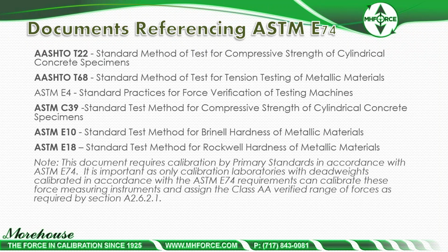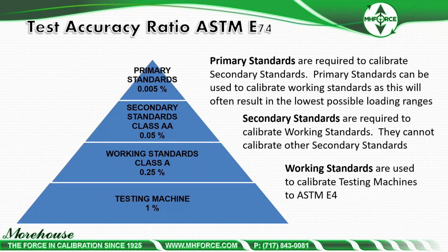Documents, jumped ahead of myself. The documents referencing E74, the standard. We're going to talk about E74 first, but here are some documents, a list of them. There's AASHTO T22, AASHTO T68, ASTM E4, ASTM C39, E10, and E18. If somebody is doing verifications to E10 and E18, their specific needs call out to have the force measuring device calibrated in accordance with ASTM E74 using deadweight primary standards. So basically what this is saying, it's in section A2.6.2.1 in E18, and there's similar wording in E10.